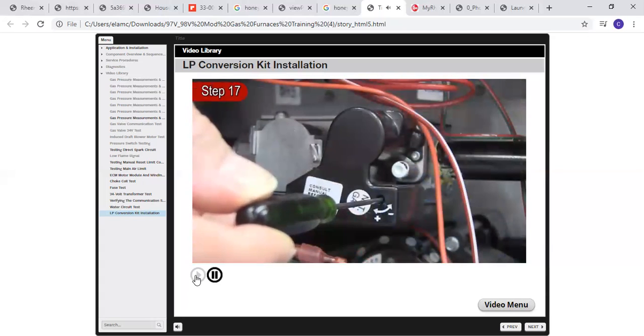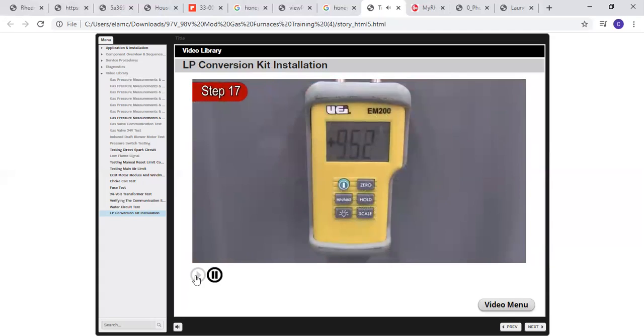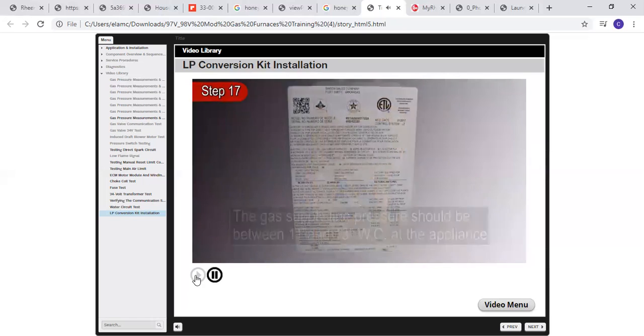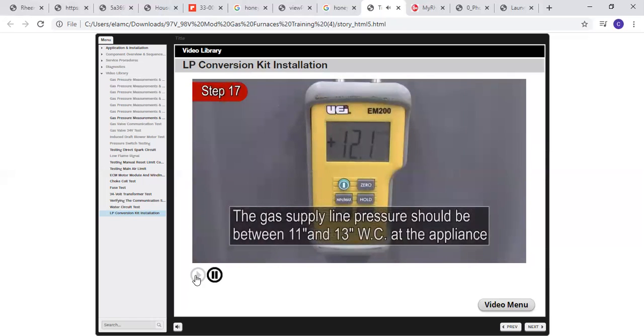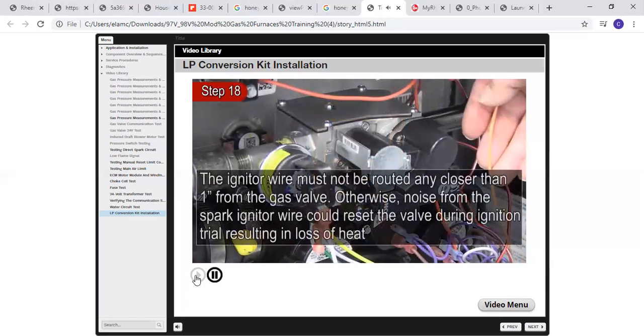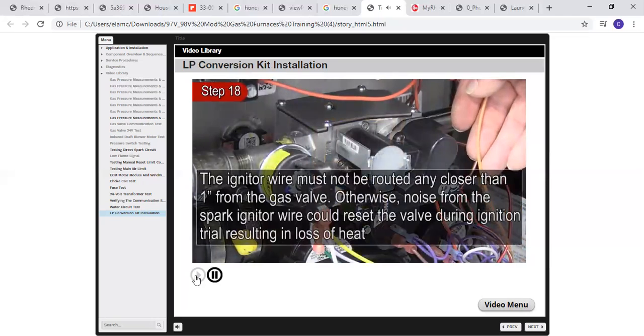Step 17. Manifold gas pressure must be adjusted to 10 inches water column after valve conversion to LP gas with furnace in operation and proper gas supply pressure. See the rating plate. The gas supply line pressure should be between 11 inches and 13 inches water column at the appliance. Step 18. Note, the igniter wire must not be routed any closer than 1 inch from the gas valve. Otherwise, noise from the spark igniter wire could reset the valve during ignition trial, resulting in loss of heat.